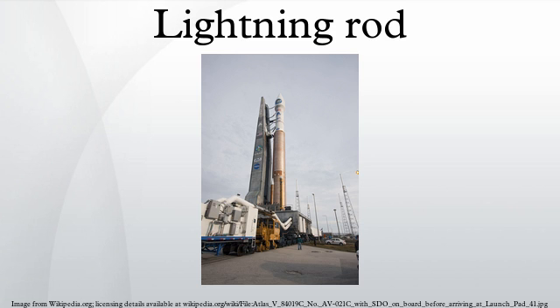Because of the high energy and current levels associated with lightning, and the very rapid rise time of a lightning strike, no protection system can guarantee absolute safety from lightning. Lightning current will divide to follow every conductive path to ground, and even the divided current can cause damage. Secondary side flashes can be enough to ignite a fire, blow apart brick, stone, or concrete, or injure occupants within a structure or building. However, the benefits of basic lightning protection systems have been evident for well over a century.